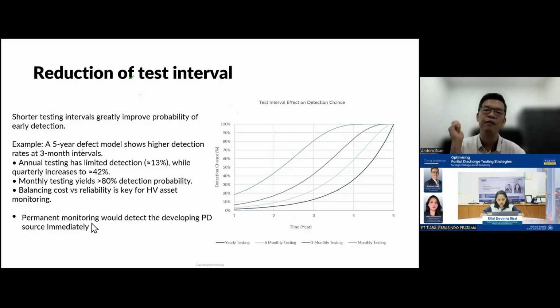Once you get PD, you want to detect it. This solution is now available - we have permanent monitoring. This permanent monitoring will detect a developing PD almost immediately. Once the PD is detectable, the permanent monitoring sensor will capture it and send you an alert, and then you can decide what you want to do next. But of course, we can't install a permanent monitoring solution on all our assets because it's very expensive, so that's why we need to plan.